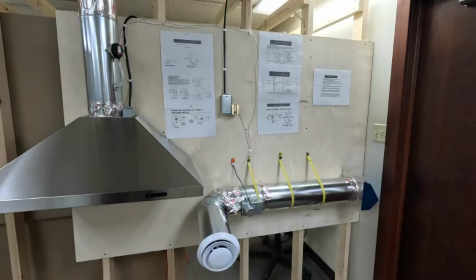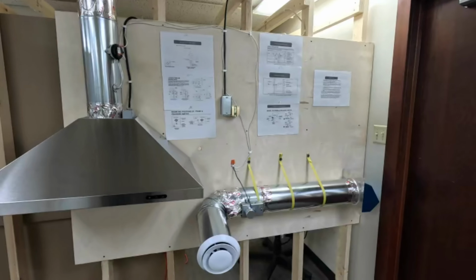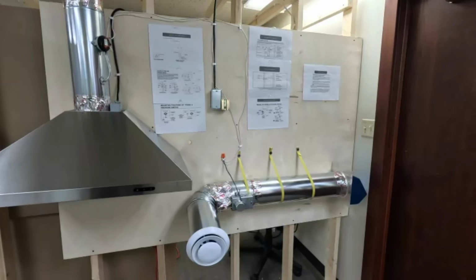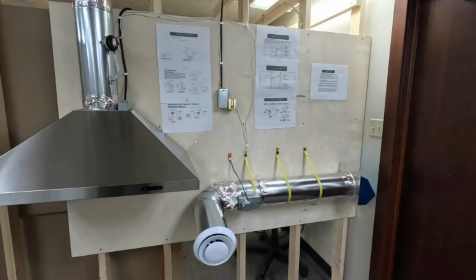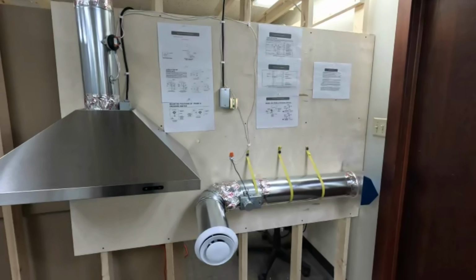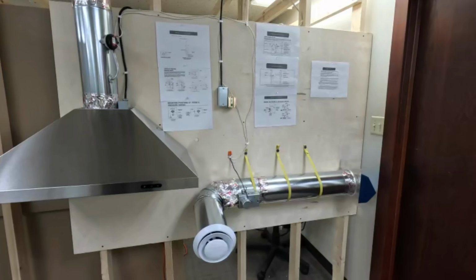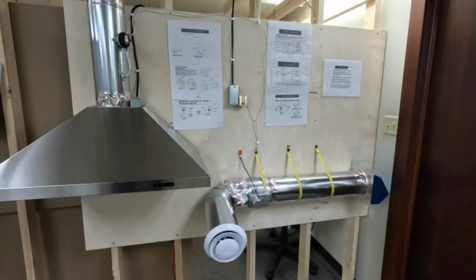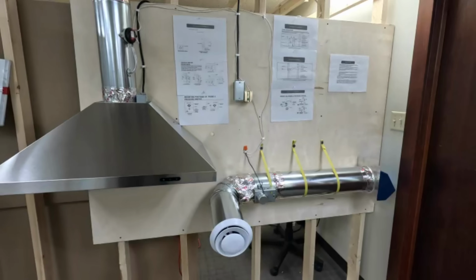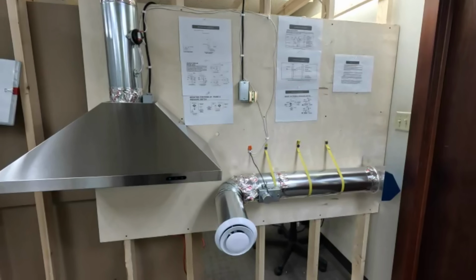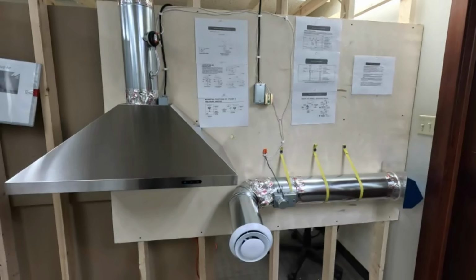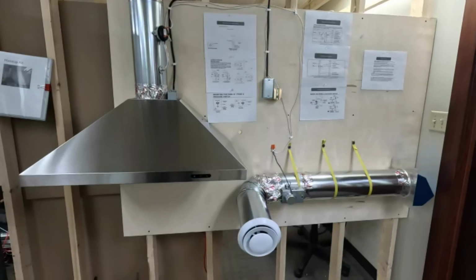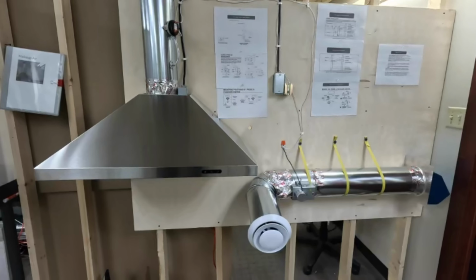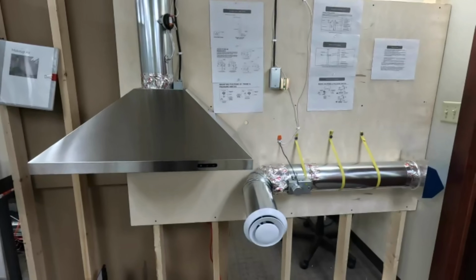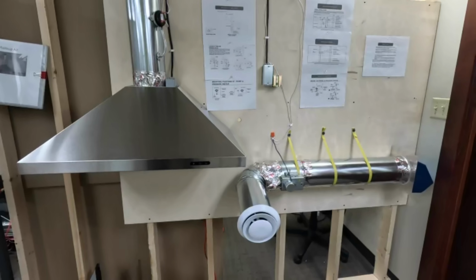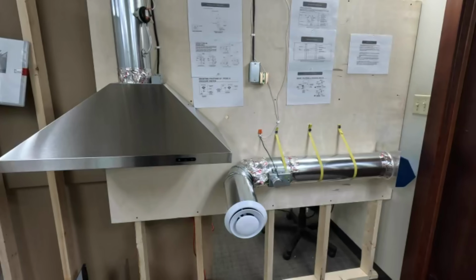Makeup air is code driven, and depending on where you live, state and county codes dictate. A lot of codes say that anything over 400 CFM, you need to bring in makeup air. The other good reason is if you're cooking over, let's just say, a 6-burner gas cooktop, and you have a 1200 or 1500 CFM range hood, and you need that much when you're cooking over equipment like that. Even if code tells you you can't have more than 400, you really want to bring in makeup air, because 400 CFM is definitely not enough to ventilate a 6-burner cooktop properly. So it's there for a purpose, and again, the main reason is to prevent negative pressure from occurring in the home.